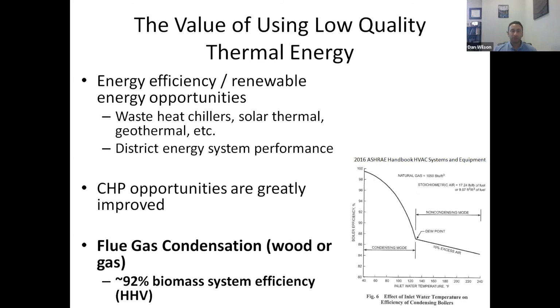As you look into trying to capture renewable energy, such as solar thermal or waste heat capture off chillers or other systems at your facility, you find those all get eliminated if you need to provide steam to the building. But if we could provide low temperature hot water to the building, we can start to pull heat from all kinds of interesting places that are either renewable or waste heat floating around our facility.